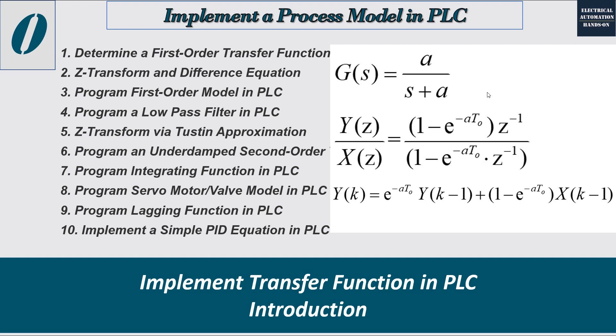Therefore, when we verify the PID function or any control function in the PLC side, we do not need any other actual hardware or any other software to simulate the process object. We can use those models running inside the PLC as the controlled object and test the control function. Once we finish the testing, we can disconnect those simulated objects and then switch to the real system. This switching can be seamless.